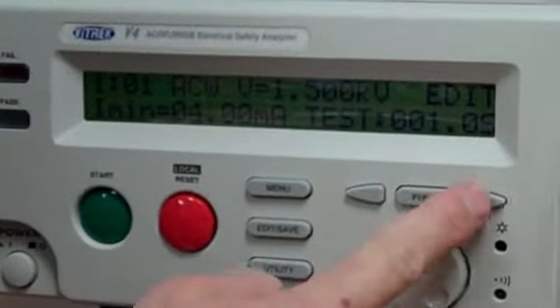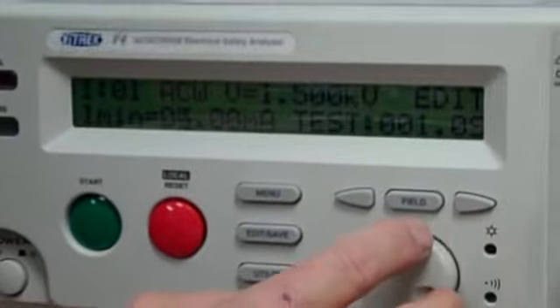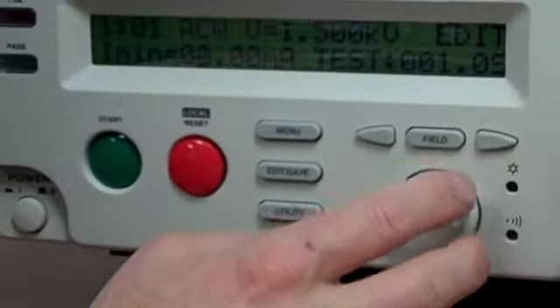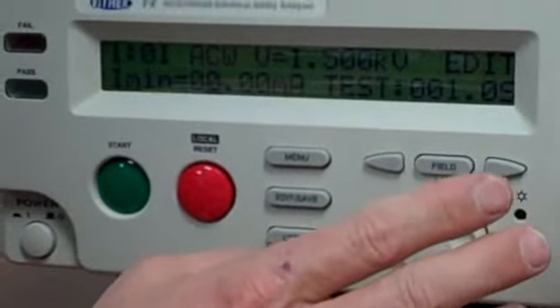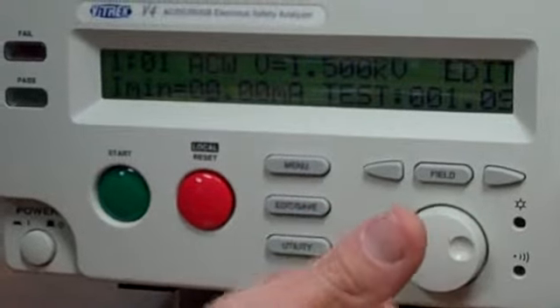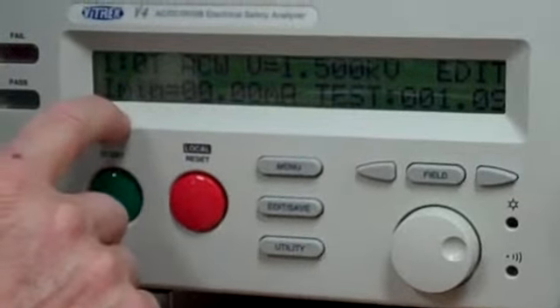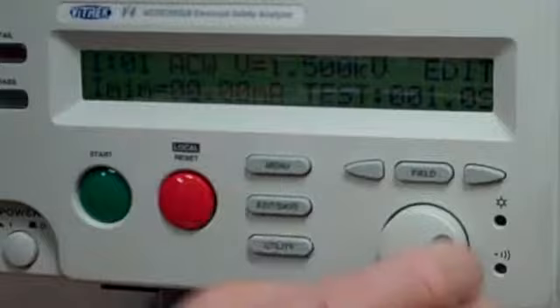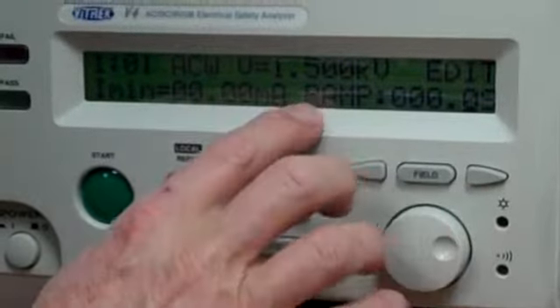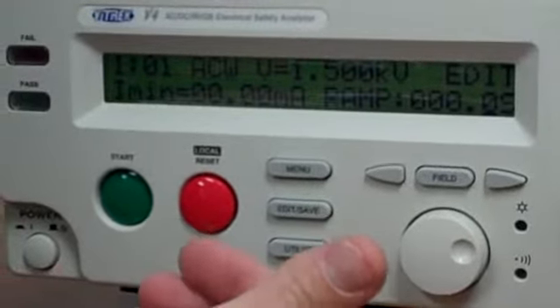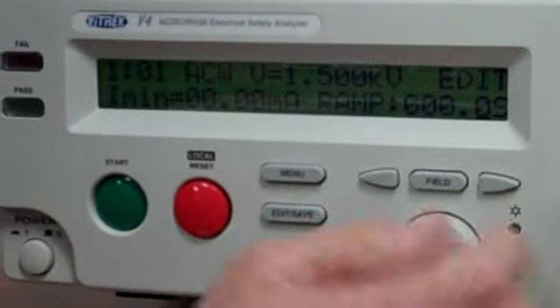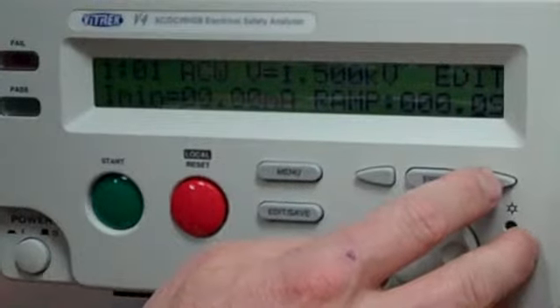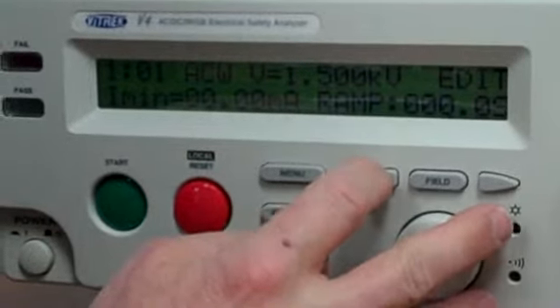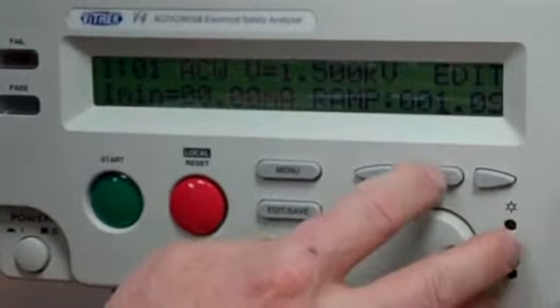I recommend setting that at 0 until you know what your baseline leakage current is, because if you get a leakage reading below the minimum limit, it's going to fail the test. So we'll start with 0. Ramp time. That's how long it takes us to go from 0 up to the test voltage. UL likes to see a 1-second ramp, so let's go over here and put 1 second in there.